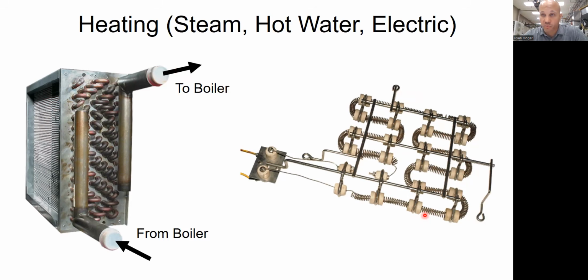Once again, based on last week, anytime someone has electric resistance heating, they should always be getting a heat pump, no matter where they live and no matter what their electric price is. It's always a heat pump when they replace it. It should never be anything else if they have an all-electric system. If they've got a gas boiler or steam boiler, there might be different math, and they may or may not benefit from a heat pump. But all electric, no-brainer. Definitely do a heat pump.